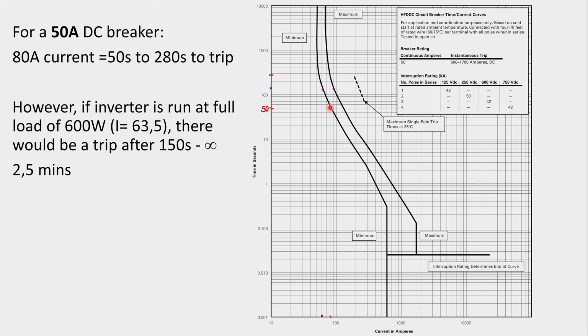Now, notice that the tripping curve has a minimum, and then if I go further up, it's got a maximum. And the reason for that is because there's something called hysteresis in the circuit breaker. The circuit breaker operates within a range or a band. So the minimum time that the circuit breaker operates will be 50 seconds. But the maximum time, depending on many factors, the temperature, the rate of rise of the current, there's many factors that influence how fast the circuit breaker will trip. The maximum time it will take is, say, about 280 seconds, because there's 100, there's 200, it's almost at the 300 mark, maybe it's like 250, 260. So it's about 50 seconds to maybe 260 seconds to trip.